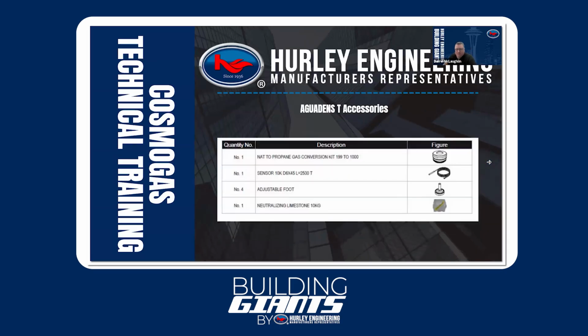This is the common kit that comes with all of the water heaters. So whenever you order one, these are not things you have to order separately. They just are automatically sent. You get the adjustable feet, the neutralizing limestone or neutralizing media. We'll get a tank sensor or system sensor that can be used for temperature control. And you'll also get the orifice for propane conversion, so if you ever need to switch to propane, you don't have to order a kit or do anything separate. You can just place this orifice in, remove the gas orifice, and then tune it to the propane standards.